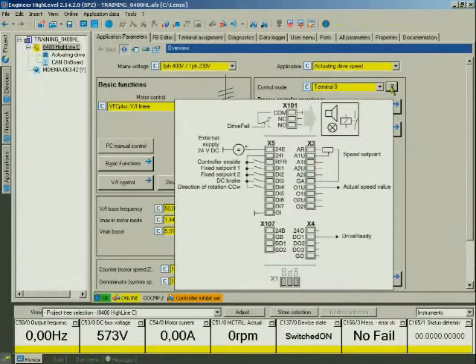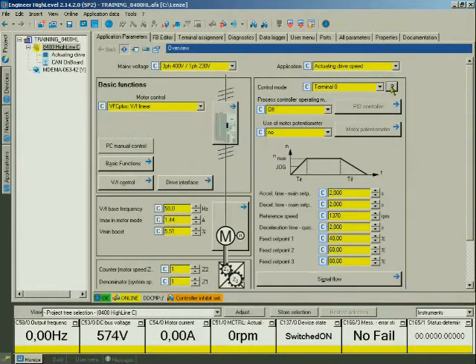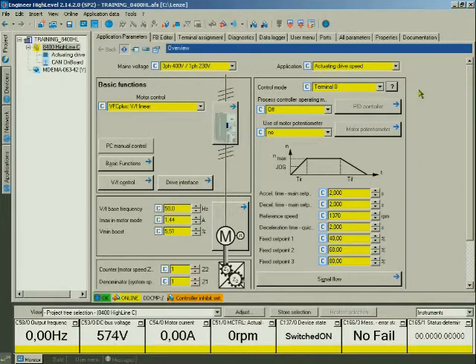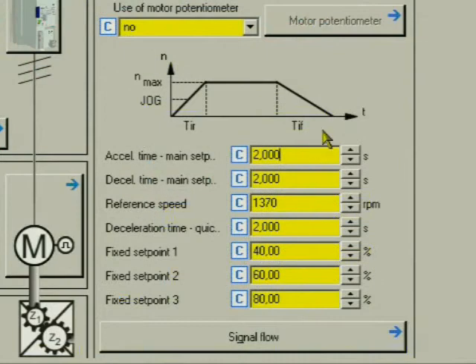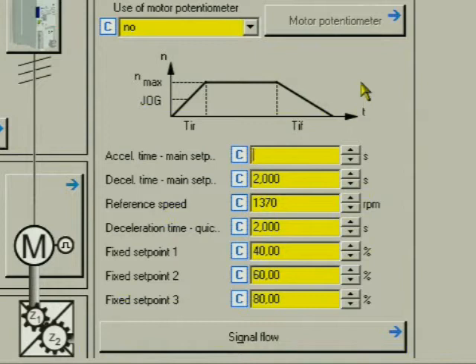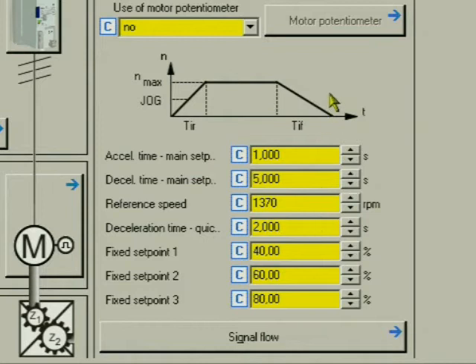We adapt some values to our drive. We accelerate more quickly and decelerate more smoothly. For this, we change the acceleration time from 2 seconds to 1 second. The deceleration time is extended to 5 seconds. For the quick stop, we select 1 second.